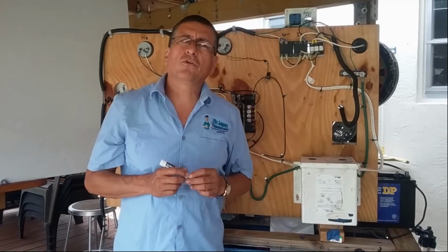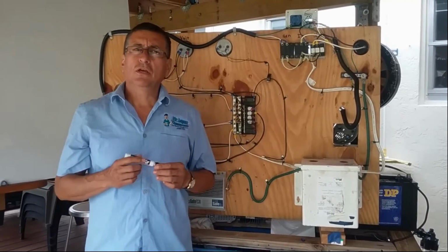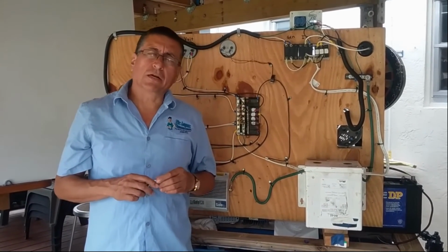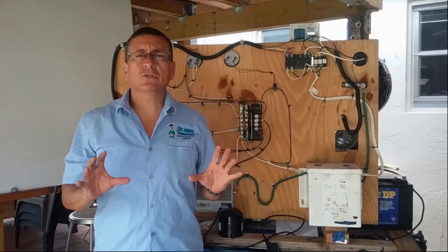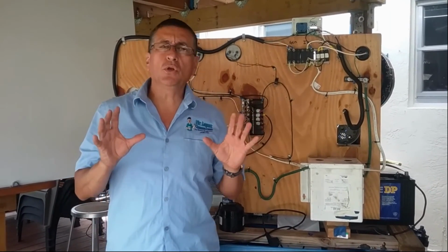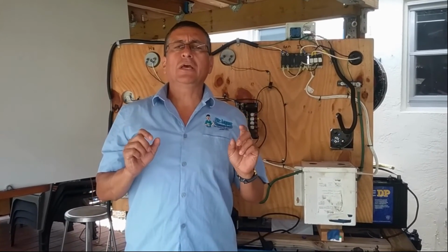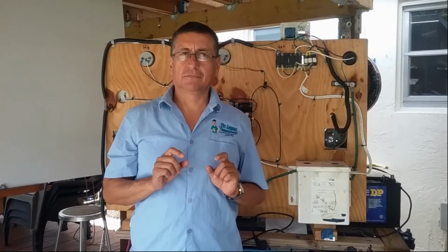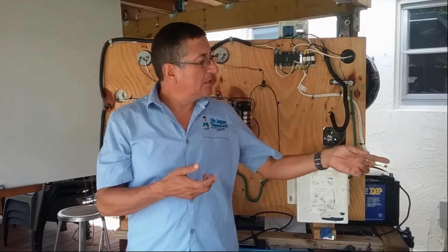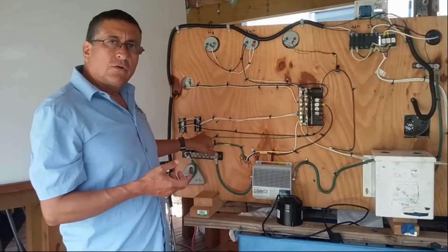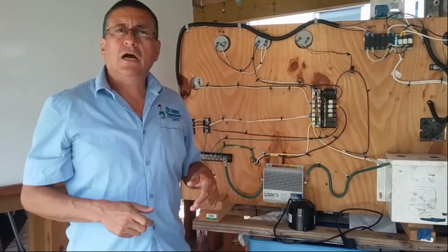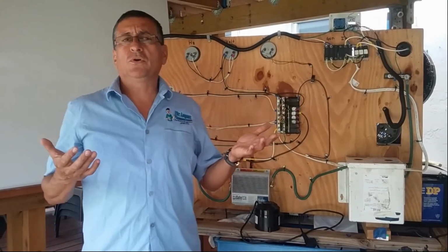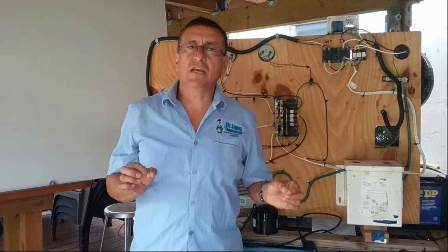What other type of transformer is commonly used in marine applications? The other transformer commonly used in marine applications is the step-down transformer. In what situation do you find a step-down transformer? The most common situation is in European boats. Remember, in European boats, each phase produces 230 volts, 50 hertz. But normally the regular outlets that you have in any socket are, if it's American, 120 volts, 60 hertz. If it's European, it's supposed to be 110, 115, 50 hertz.